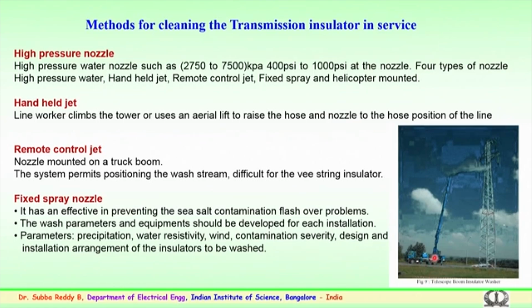So, suitably the truck is adjusted to clean the insulators, either tension or suspension type, but this has a bit of difficulty in case of V type of string, where suitable arrangements have to be made. So, there are also fixed spray nozzles which are employed by the utilities. These are effective in preventing, particularly, sea salt. So, the transmission lines which run near the sea coast, where a lot of salt contaminants get accumulated over a period, normally use these fixed spray nozzles to clean these contaminants to prevent flashover problems.